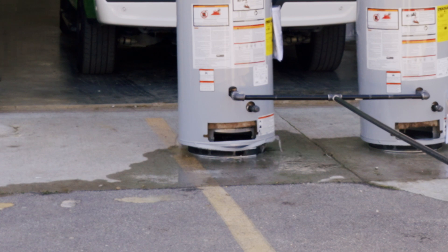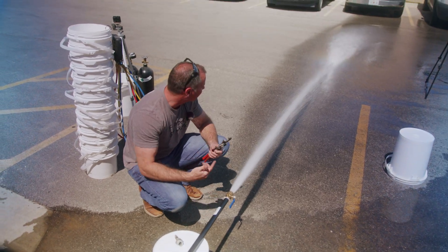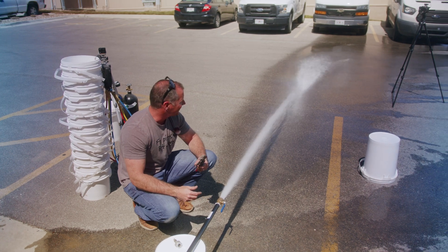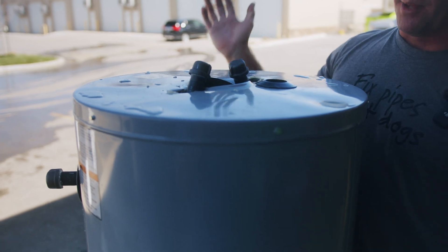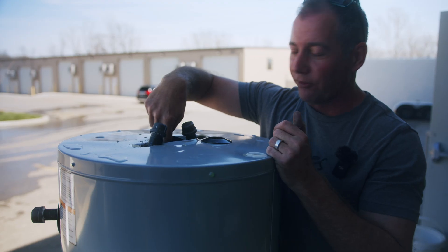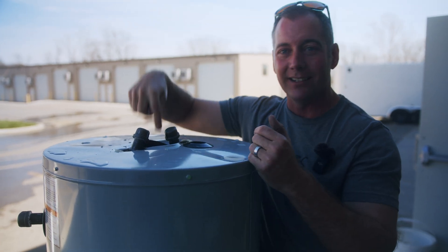The pro grade heater just let go. If you have any questions as to how much pressure was in there, we just shot water all the way across the parking lot — this isn't a pressure washer or anything, just some tanks we put together. This is the pro grade unit: these nipples started out looking straight up, now they're bent and pulled over. They actually ripped into the metal. The flue connection is now down inside the heater.